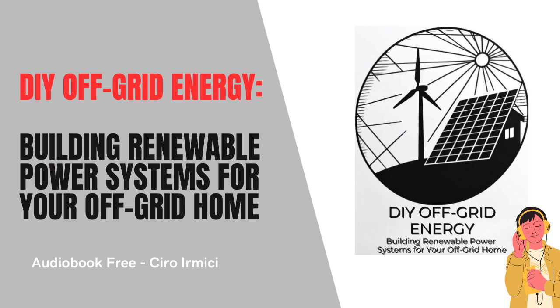For example, a refrigerator or air conditioner may require a significant surge of power when the compressor starts up, even if its regular operating power is much lower. An inverter must be capable of handling these surges without tripping or shutting down. To determine the right inverter size, start by calculating your total continuous power needs based on the wattage of your most commonly used appliances. Then, factor in the highest surge requirement to ensure that your inverter can handle peak loads. It's often recommended to choose an inverter with a capacity slightly above your calculated needs to provide a buffer for unexpected surges or future additions to your system.